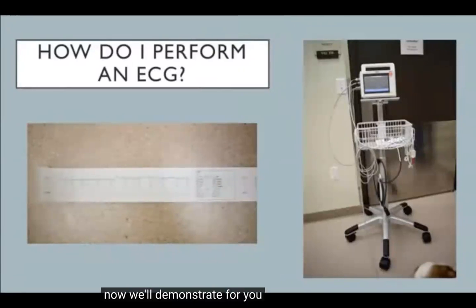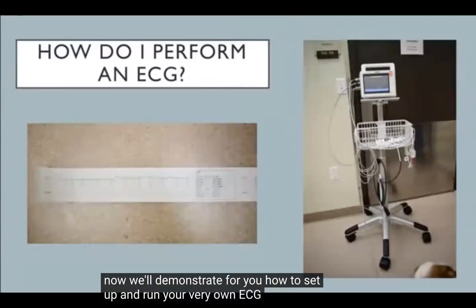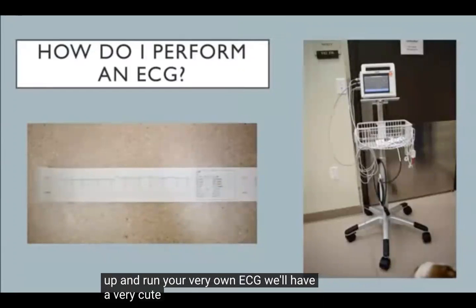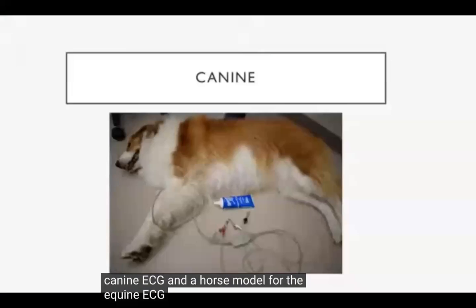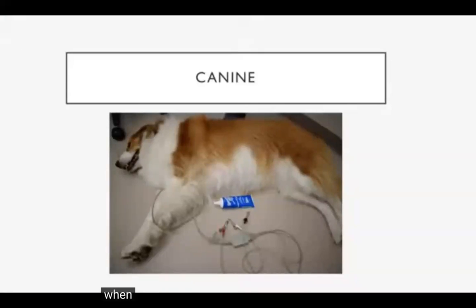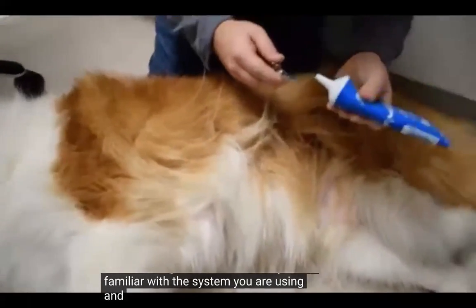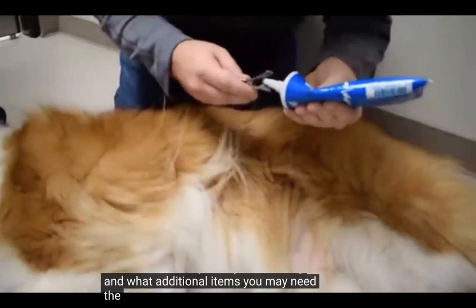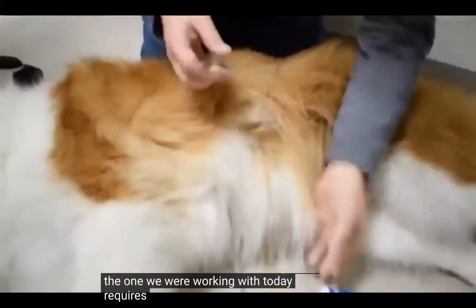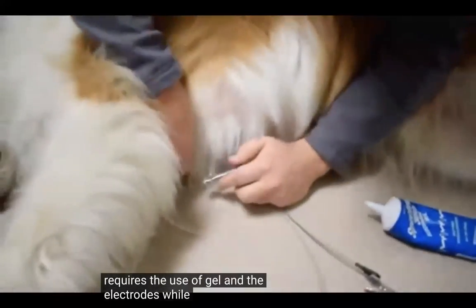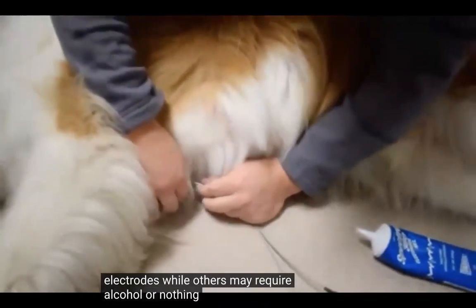Now we will demonstrate for you how to set up and run your very own ECG. We'll have a very cute canine volunteer for the canine ECG and a horse model for the equine ECG. When running an ECG, make sure you are familiar with the system you are using and what additional items you may need. The one we are working with today requires the use of gel on the electrodes, while others may require alcohol or nothing at all.